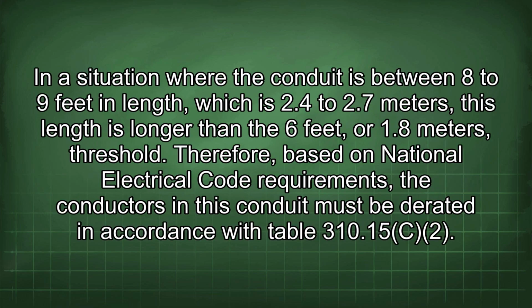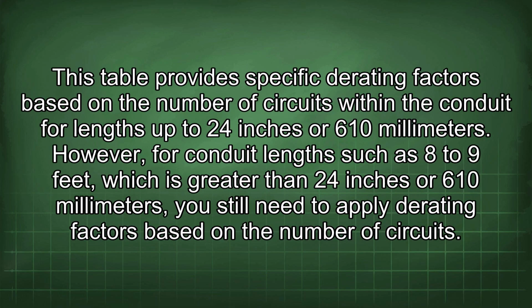310.15c2. In a situation where the conduit is between 8 to 9 feet in length, which is 2.4 to 2.7 meters, this length is longer than the 6 feet, or 1.8 meters, threshold. Therefore, based on National Electrical Code requirements, the conductors in this conduit must be derated in accordance with Table 310.15c2. This table provides specific derating factors based on the number of circuits within the conduit for lengths up to 24 inches or 610 millimeters.